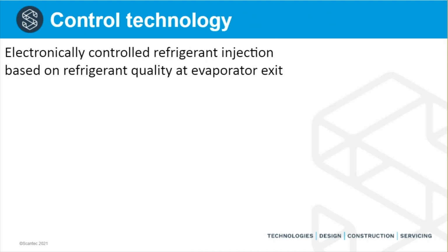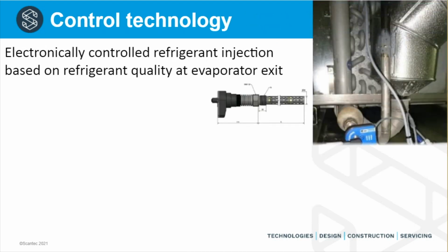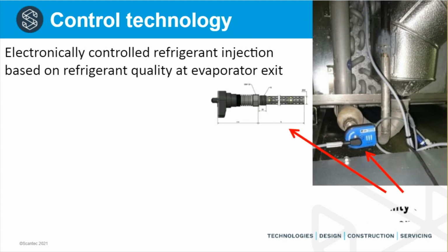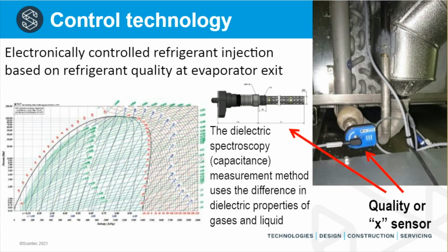May I mention before that we do not control the refrigerant injection into the evaporator by means of superheat control. We use some sensors that are able to measure the X value, or the quality value, of the vapor leaving the evaporator, and convert the quality signal to a signal that we can feed into the centralized control system, the 4 to 20 milliamp signal.